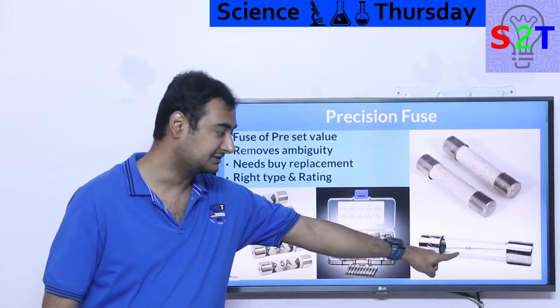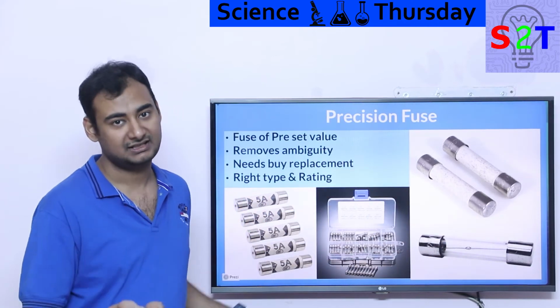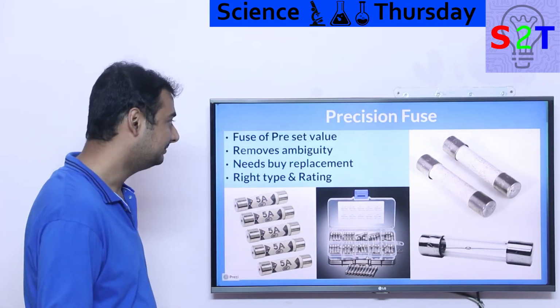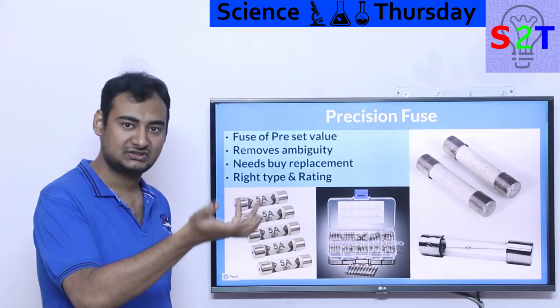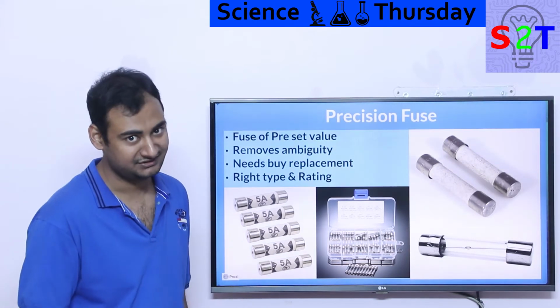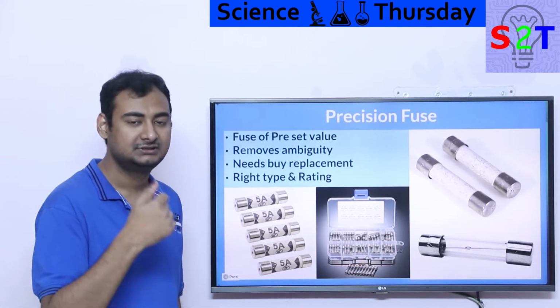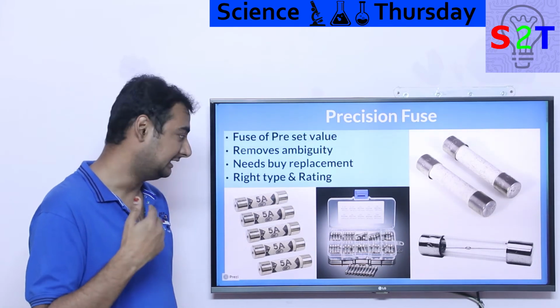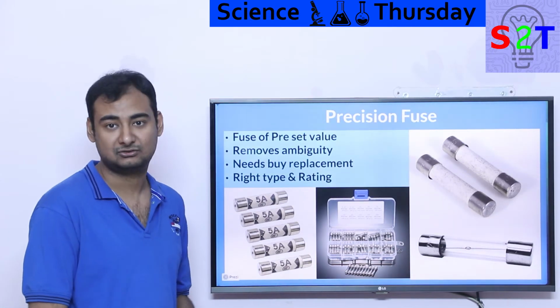You could end up in a scenario where instead of using that slow acting fuse, you put in a fast acting one, and it doesn't work. So be mindful that this can come down to a person making a mistake or not paying attention. They have to know the type, the rating, and all that, because many times the form factor could be exactly the same.